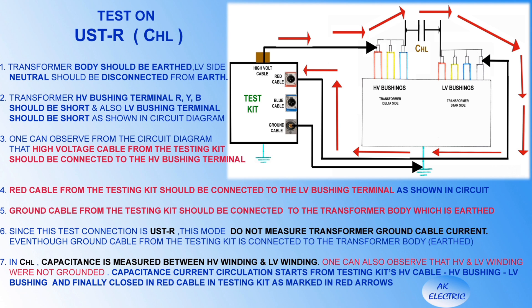In this slide we will see the test on USTR mode, CHL type. Transformer body should be earthed and LV site neutral should be disconnected from earth. Transformer HV bushing terminals RYB should be short-circuited, and LV bushing terminals also short-circuited as shown in the circuit diagram. The high-voltage cable from the testing kit connects to the HV bushing terminal, the red cable connects to the LV bushing terminal, and the ground cable connects to the earthed transformer body. Since this is USTR mode, ground cable current is not measured. In CHL type, capacitance is measured between HV winding and LV winding — both windings are not grounded. Capacitance current circulates from the test kit's HV cable through HV bushing, LV bushing, and closes in the red cable, as marked by red arrows.